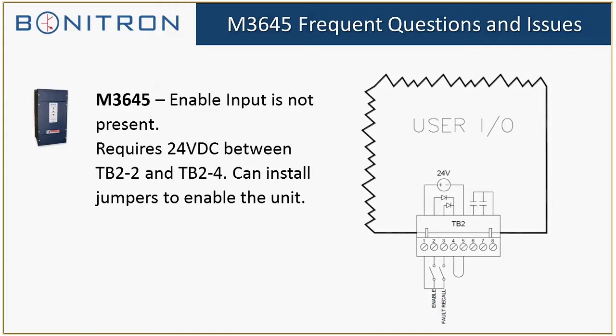The only real issue we ever had with these 3645 in terms of installation is basically just the enable input. It used to be that we did not send these out with these units jumpered. We would allow the customer to basically be able to install the jumpers and remotely enable or disable them as they saw fit. However, we kept on getting calls and calls about these, so now all new 3645s will go out with the jumpers already in place. So the jumpers that we send out with the unit are between 1 and 2 and 4 and 5. This connects to the little 24 volts inside, and basically the unit is self-enabled. If the customer does want to control the enable, they can just take the jumper out of 1 and 2 and then install their switch and run that to their PLC, and from there they can enable or disable the M3645 as they see fit.